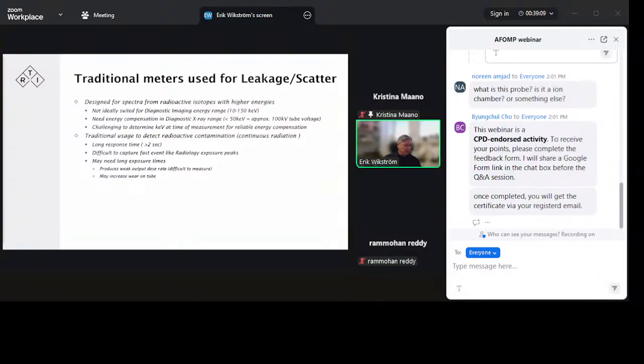And if we need to crank it up for a long period of time, for longer exposures, that increases the wear on the tube. And then we've got mechanical design. Typically, there would be ion chambers used there, but they need temperature and pressure compensation in addition to the energy compensation to give a proper value. If it's a pressurized ion chamber, of course, then it's also hazardous cargo. So that puts challenges on shipping back and forth to sites and also to calibration laboratories.